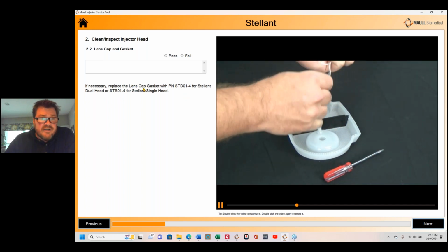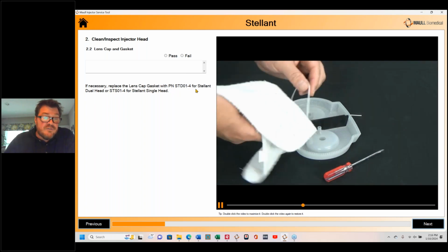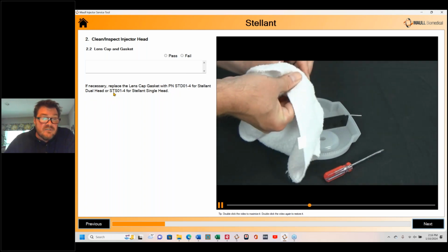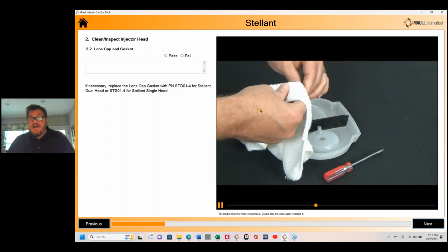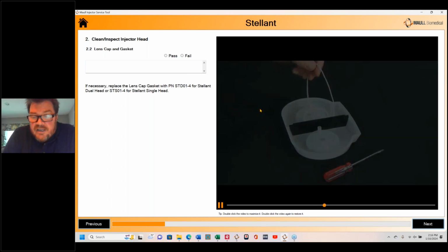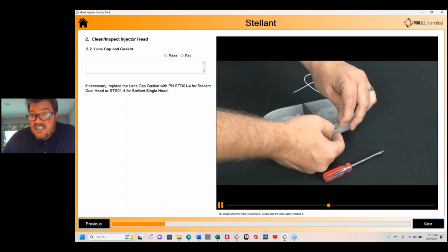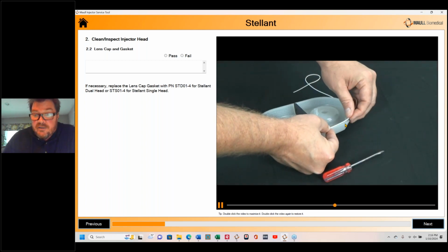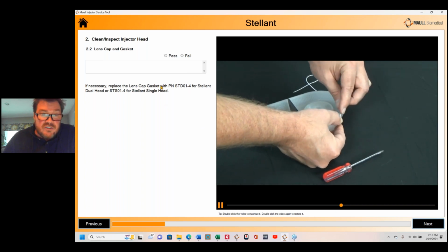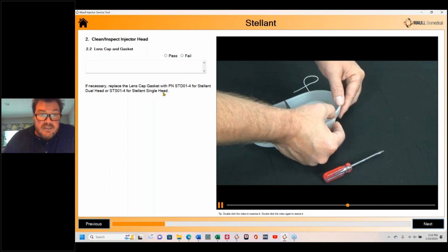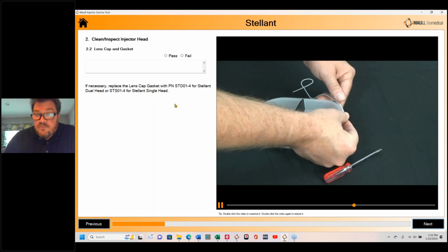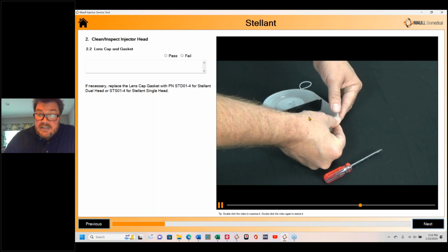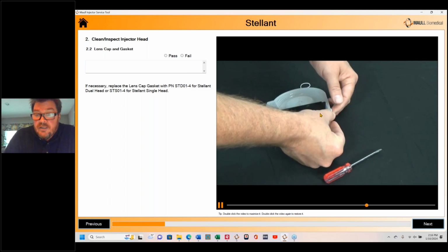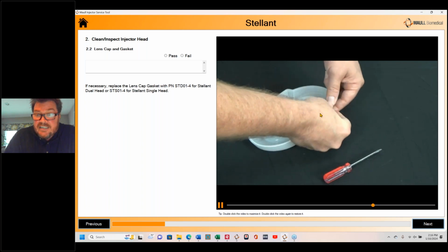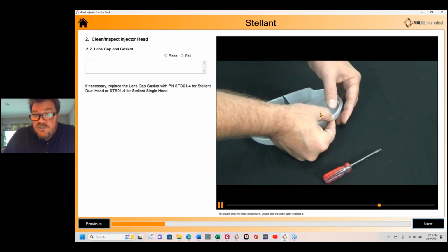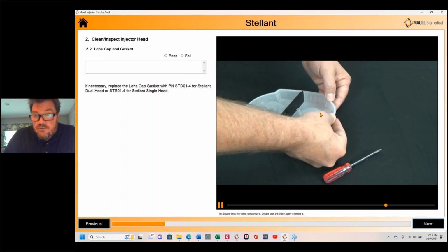And over here it says, if necessary, replace the lens cap gasket with part number STD01-4 for the Stellant head, or STS01-4 for a single head. Maull Biomedical, we sell the PM kits for these contrast injectors, and for these gaskets, whenever we're showing a gasket or some component that needs to be inspected or replaced on a regular basis, we typically show the part number for that in the text over to the left. So then obviously here we took the gasket off, cleaned it, inspected it, make sure that it's still good to go. And then this obviously is just showing us putting the gasket back on. If the gasket were torn up or in bad condition, then the gasket would just be replaced.